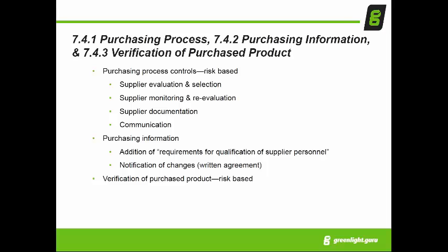You need to have appropriate controls in place, which may drive you to do more activity as far as supplier qualification and monitoring. You may need to do more work on supplier audits and things of that nature. So again, what you do needs to be defined, needs to be proceduralized, and it needs to be directly commensurate with the risk that material, product, or service that you're buying poses to your medical device.